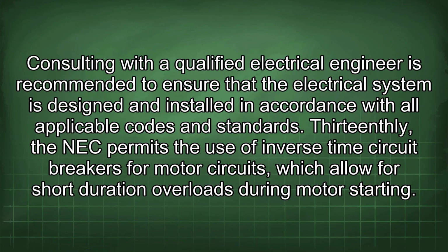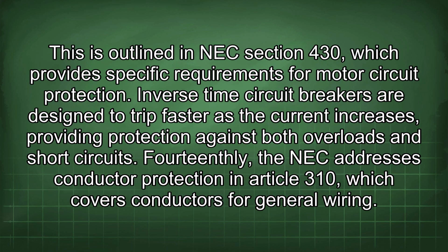13thly, the NEC permits the use of inverse time circuit breakers for motor circuits, which allow for short duration overloads during motor starting. This is outlined in NEC section 430, which provides specific requirements for motor circuit protection. Inverse time circuit breakers are designed to trip faster as the current increases, providing protection against both overloads and short circuits. 14thly, the NEC addresses conductor protection in Article 310, which covers conductors for general wiring.